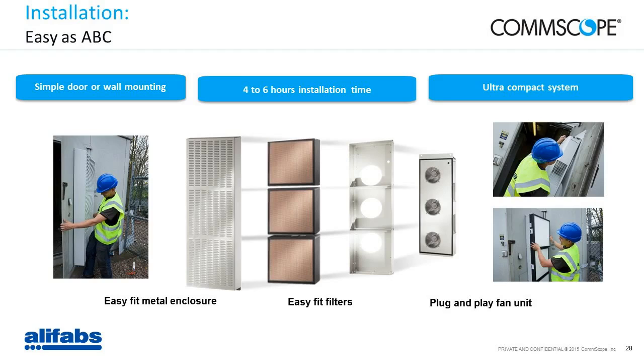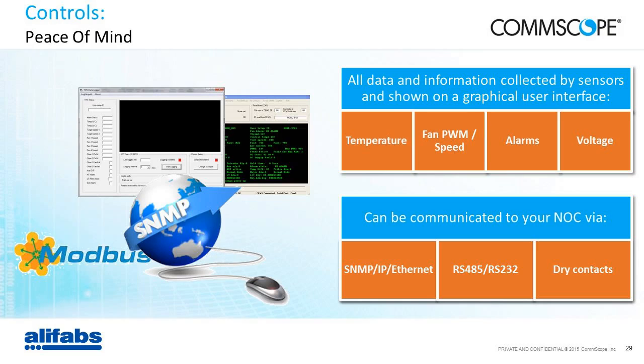So finally, how about using the system? What does it mean when it's installed on your site? Peace of mind, the most important thing. Fit and forget. When you have a system, you don't want to constantly have to look after it. So temperature, fan PWM, fan speed, all the alarms and the voltage can be fed back to your network operating center. They can be fed back via different types of communication system, whether over IP, RS485 or dry contacts. So the system can have an IP address, and you can adapt it to your system. You can then read all of this data out of your monitoring system.